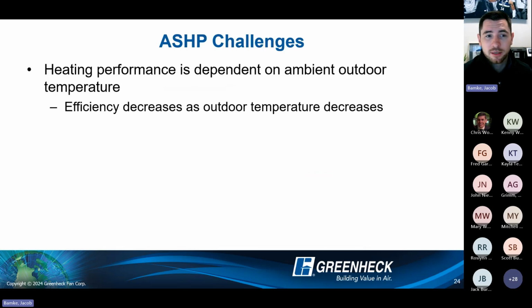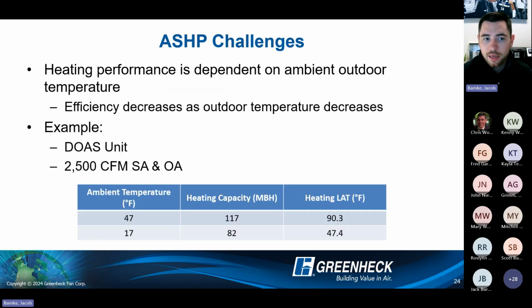But there are some challenges with this as well. So heating performance is directly dependent on the ambient outdoor temperature. So one thing that happens is efficiency will decrease as your outdoor temperature decreases as well. So as an example, I have a true DOAS unit. This one does not have energy recovery. You have 2,500 CFM, 100% outside air. At 47 degrees, so a mild condition when I still need some heating, I have enough capacity to get all the way up to 90.3 degrees leaving air temp.